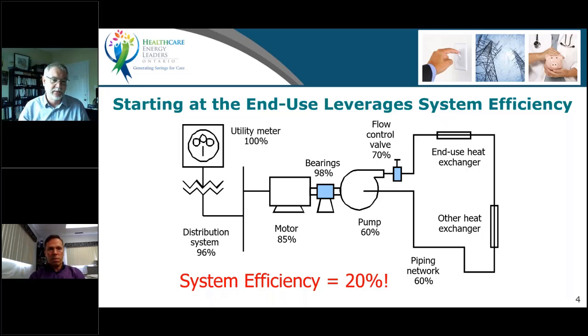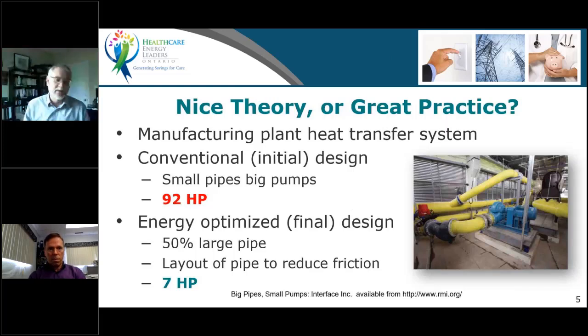a lot of pumps. And I want to step into a situation where a manufacturing plant was being designed. It had about 90 horsepower of pumps in the original design. And they asked the designers to go back and think about the size of the pipe, right? And the bends and turns in the pipe. So the friction in the driven system being the piping network. When they did that, they started off with 92 horsepower, as I said, but then the final design, which was optimized for energy, was 7 horsepower of mover, basically in that system. That is an incredible difference.